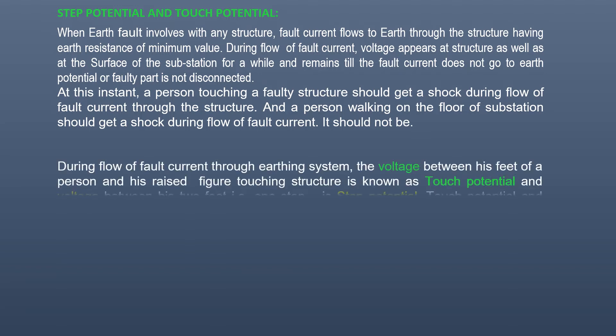During flow of fault current through earth system, the voltage between his feet of a person and his raised finger touching structure is known as touch potential, and voltage between his two feet, that is one step, is step potential. Touch potential and step potential is minimized by minimizing earth resistance using earth mat.